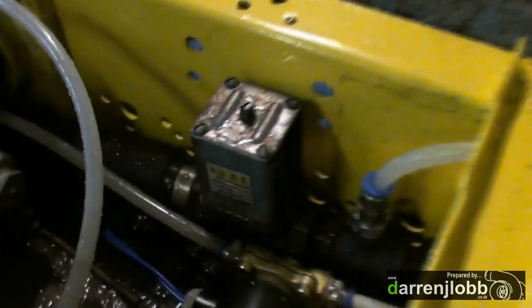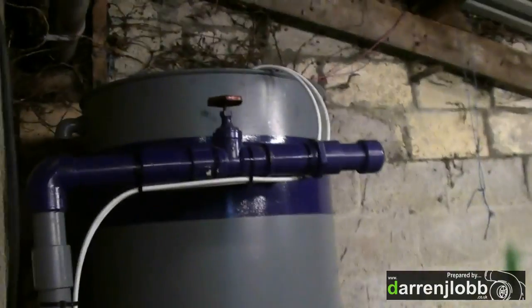Underneath this cover, which I just made the other day, it basically gets teed underneath, so it comes in teed, and you've got a feed and a return from each brake via the thermostat valve. That has a probe which sticks into the bottom of the brake, senses the temperature and regulates it inside the heat exchanger, and then it returns back into the tank again.